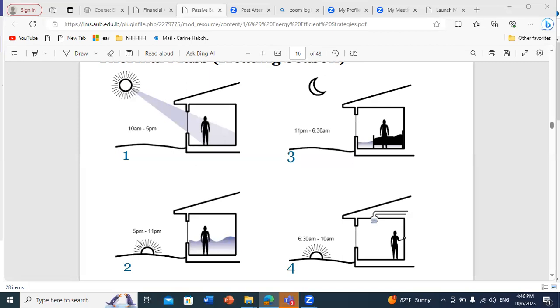Then from 5 p.m. to 11 p.m., the thermal mass will release back the stored energy in order to allow an acceptable temperature within the space. After this, the heat release will be reduced with time. If you study the heat release, it will be optimal in the first few hours, and with time it will be reduced, because the heat release is related to the difference in temperature between the thermal mass and your inner space.